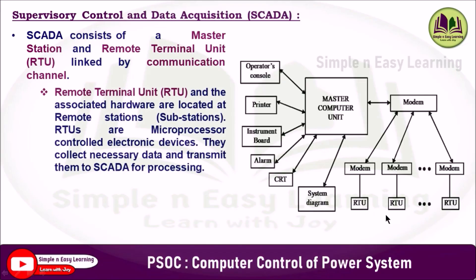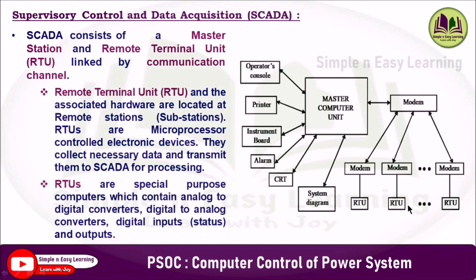The remote terminal unit and the associated hardware are located at remote stations, generally in substations. These RTUs are microprocessor-controlled electronic devices that collect necessary data with the help of sensors and transmit them to SCADA for processing. RTUs are special-purpose computers which contain analog-to-digital converters, digital-to-analog converters, and digital input and output status.